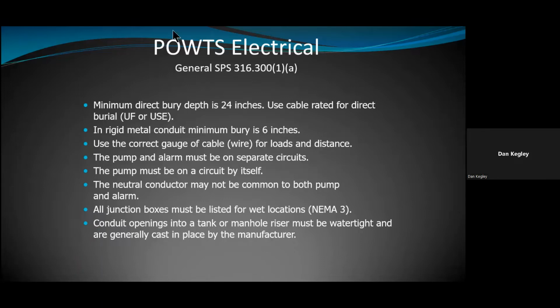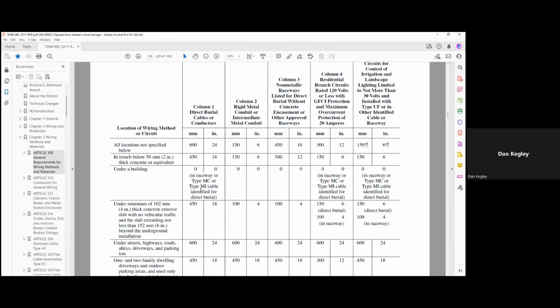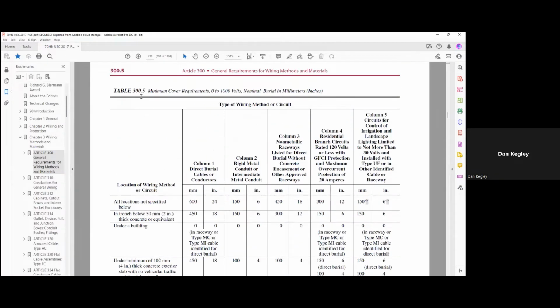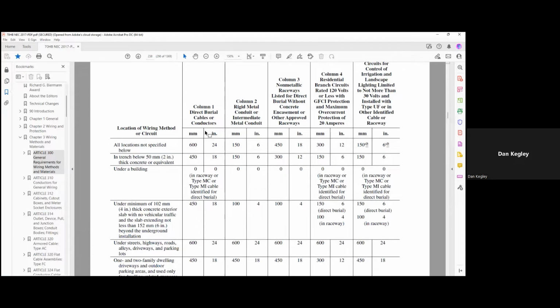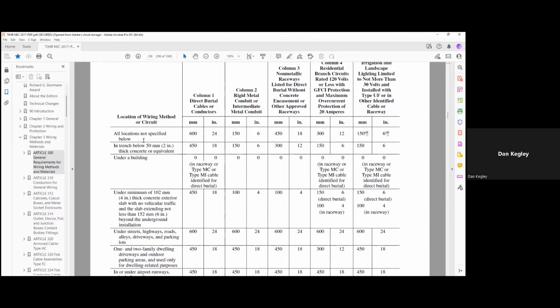I wanted to share this quickly with you, so I'm going to switch over to this. This is the actual code itself under Article 300. This is Table 300.5, minimum cover requirements for 0 to 1,000 volts nominal. Under column one, direct burial cable or conductors, and on the left-hand side, all locations not specified below is 24 inches, which is what's listed there.